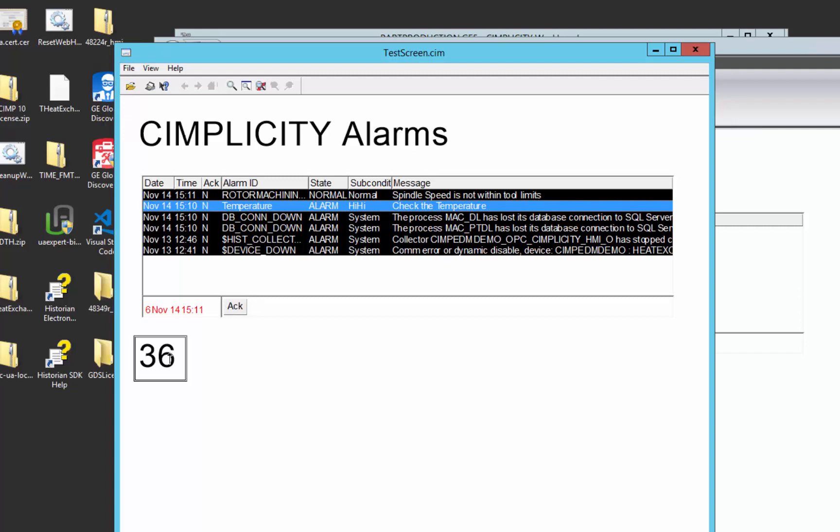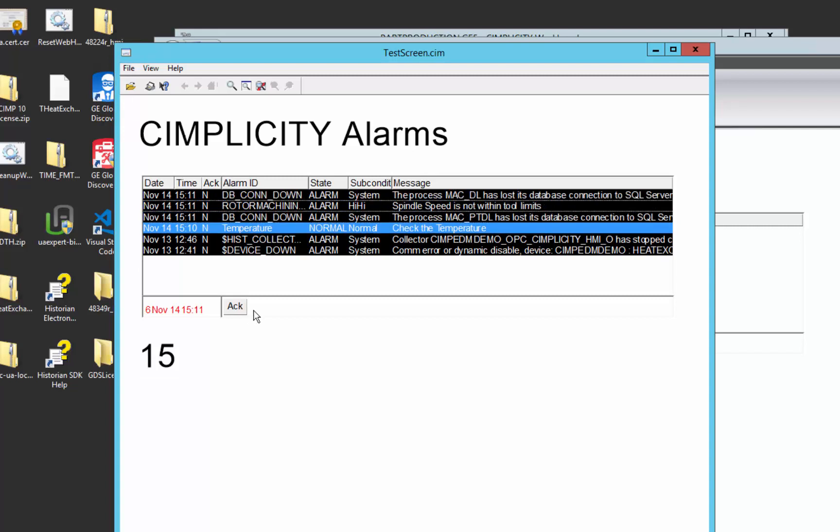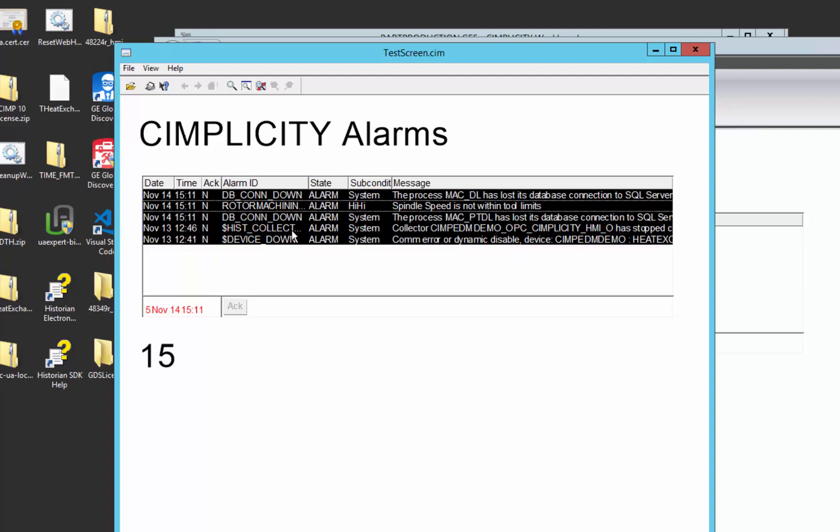If I bring that value back down to the normal operating range, you can see it goes into a normal state but doesn't leave the window because we've got our system configured to require an operator to acknowledge an alarm before it goes out of the queue. So if I acknowledge that alarm, you can see it disappears.